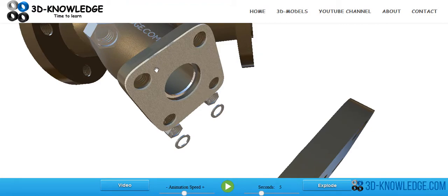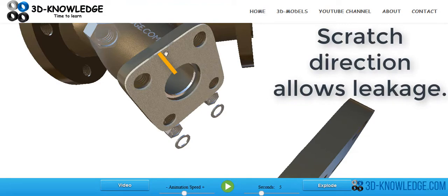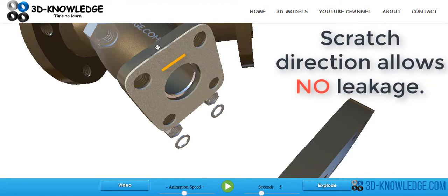If it is damaged, you're going to need to slowly scrape it off. And ideally, when you're scraping, you don't want to be scraping in this direction to get the gasket off. What you want to be doing is scraping in this direction. That way, if you do put a scratch in the metal plate, you're not going to take it all the way from, for example, here, the interior to the exterior. That's creating a path for the fluid to flow down and escape. If you scratch this way and you scratch too deep, the fluid's probably not going to be able to leak into this area, and even if it does, it's only going to leak along here.